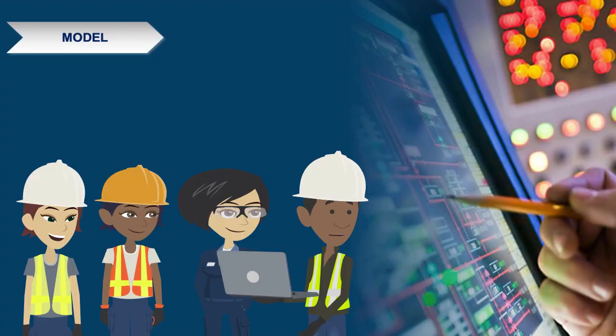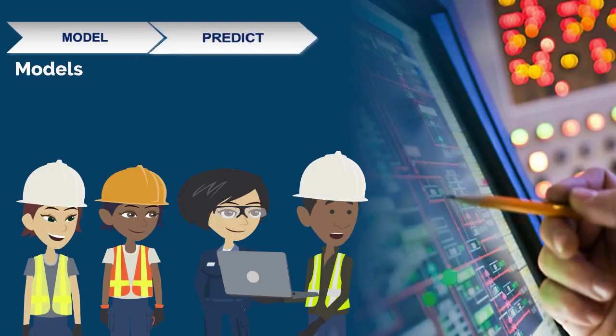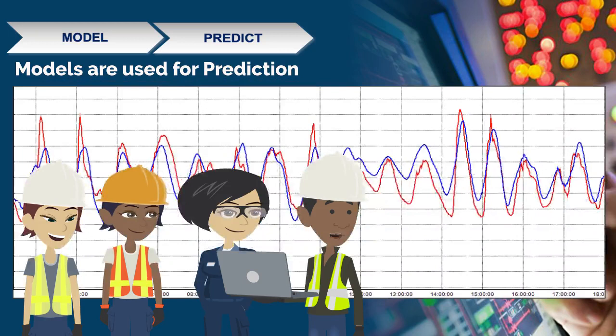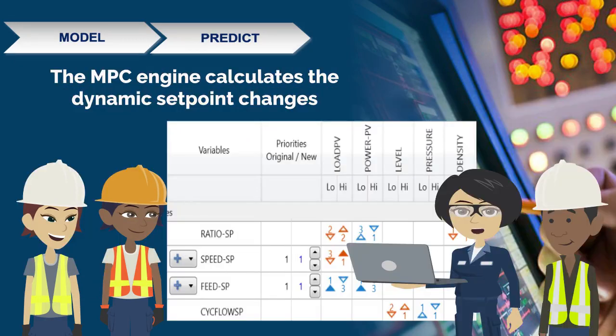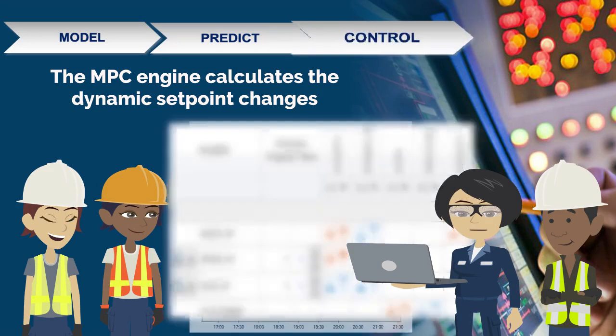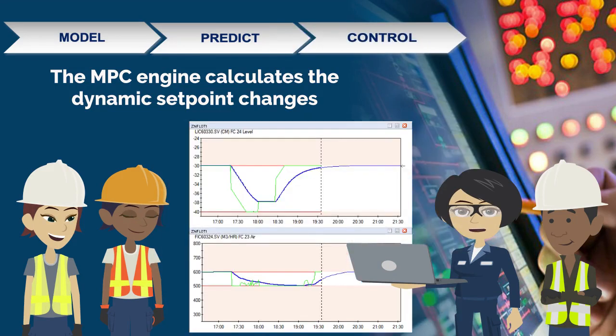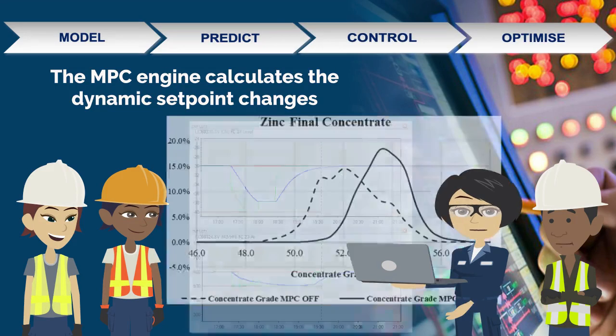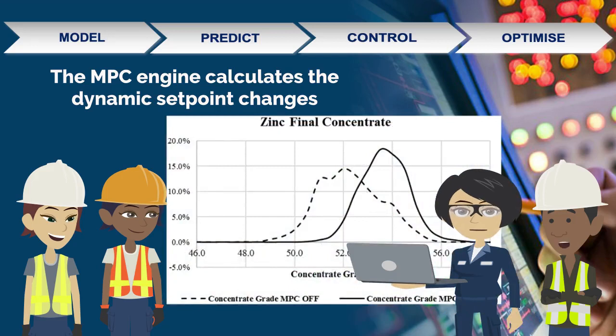Because the models are dynamic, they look into the future — this is a rarity on a process plant. The MPC engine calculates the dynamic set point changes to move the process safely to the optimum point. So the MPC calculates where to go and how to get there, all without operator intervention.